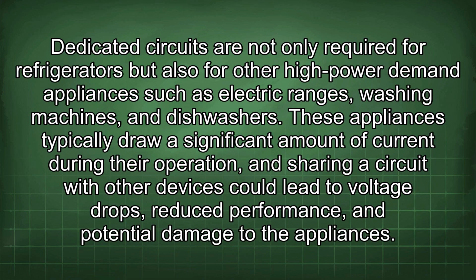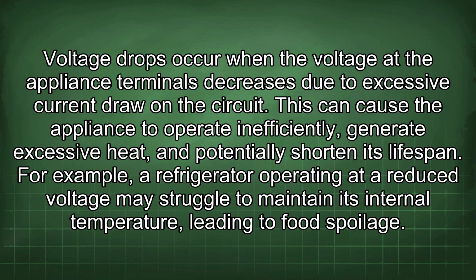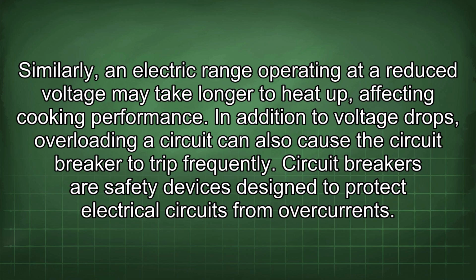Dedicated circuits are not only required for refrigerators but also for other high power demand appliances such as electric ranges, washing machines, and dishwashers. These appliances typically draw a significant amount of current during their operation, and sharing a circuit with other devices could lead to voltage drops, reduced performance, and potential damage to the appliances. Voltage drops occur when the voltage at the appliance terminals decreases due to excessive current draw on the circuit. This can cause the appliance to operate inefficiently, generate excessive heat, and potentially shorten its lifespan. For example, a refrigerator operating at a reduced voltage may struggle to maintain its internal temperature, leading to food spoilage. Similarly, an electric range operating at a reduced voltage may take longer to heat up, affecting cooking performance.